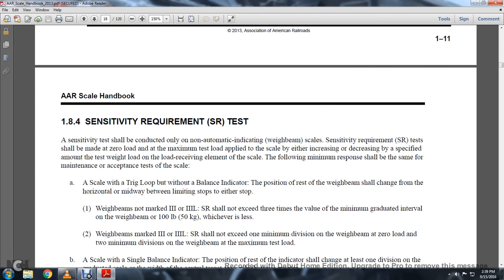1-8-4: Sensitivity Requirement (SR) Test. The sensitivity test shall be conducted only on non-automatic-indicating (weighbeam) scales. Sensitivity requirement testing shall be made at zero load and maximum test load applied to the scale by either increasing or decreasing the amount of test weight load on the load receiving element of the scale.